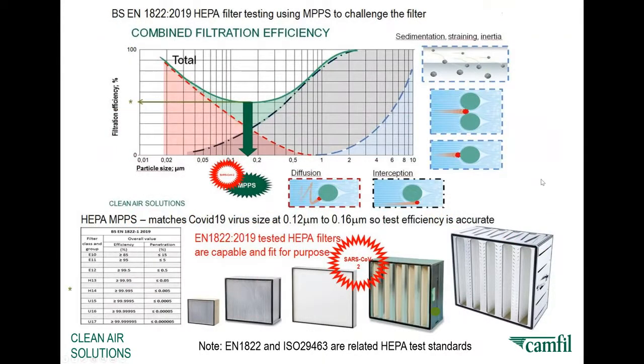We already have widespread use of the recirculation of air in freestanding air purifiers and air cleaners, as has been demonstrated with that Addenbrooke study we were just looking at. These are extremely effective in terms of removal of viral particles. But instead of looking at the actual viral particle itself, which is around 0.12, 0.16 microns here, if we're finding out from that study that you've got to go above 1 micron, then you've got incredibly high removal efficiencies up to this range. And indeed ISO 16890 filters are extremely efficient in this particle size range. So I think we're just really neglecting a really good weapon in our arsenal for keeping air clean and healthy for people to breathe without risk to health by investigating the potential we have here.